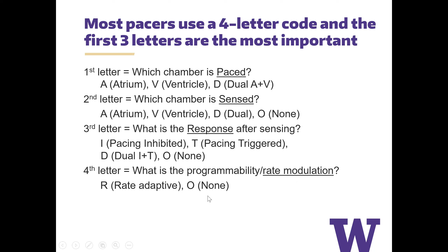And then the fourth letter, which is basically an on and off binary kind of letter, is the rate adaptive mode. Is it on, which is R, or is it not on, which is O? So this is kind of the schematic. A better way to represent it, I call this Medtronic. What you can see is the first letter is for pace, the second letter is for sense, the third is for response, and the fourth is for rate. If you look at the table down here, these are the options, and what's highlighted in blue are the most common types of pacing configurations. So you would pick one in the blue here, one in the blue here, one in the blue here, and one in the blue here. And again, different combinations of that will give you different pacing configurations.